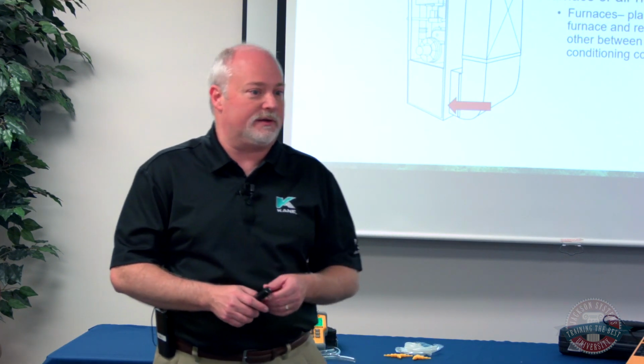So that does give you enough differential there to find out if you've got a leaky duct system. Typically, you're going to measure inside the house and measure outside to see, when our blower comes on, how we're losing air. If we've got a leaky duct system, that's going to show our negative pressure. So that's one reason we actually upgraded that instrument. That's a great question. Thanks.